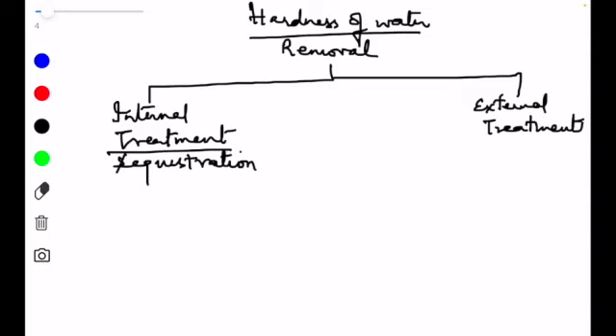In this process, an ion is prevented from showing its original character by converting it into a more soluble salt, which is done by adding an appropriate reagent. Internal treatment can be done by two processes: first, appropriate chemicals are added to the boiler water to precipitate out the hardness-causing salts, avoiding scale and sludge formation; second, the problem-causing cations are converted into compounds that stay in dissolved form and do not deposit as scale or sludge.